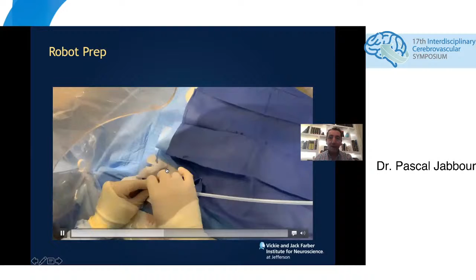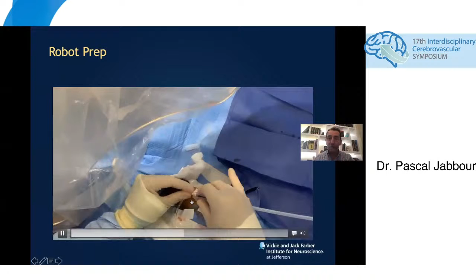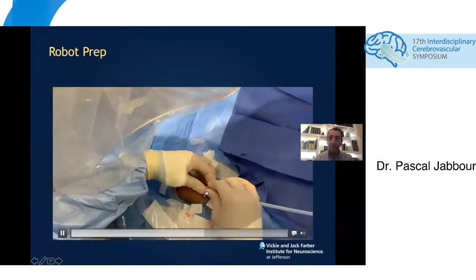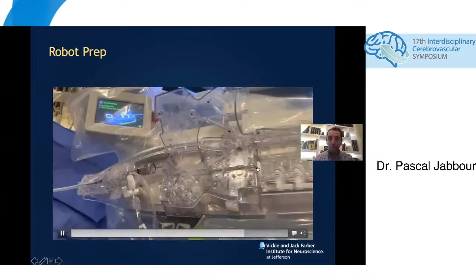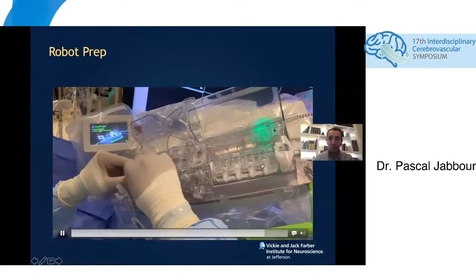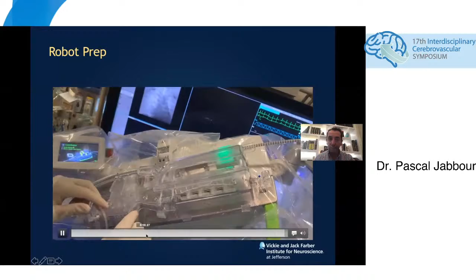Now I'm putting in my guide catheter. I'm pulling the sleeve all the way and locking the sleeve in the sheath. As you see here, this is a snuff box sheath. So it's locked here. Now we're going to load whatever devices we want to put there. This is ready to load. That's the micro wire getting loaded. That's the device getting loaded here, and everything is closed.